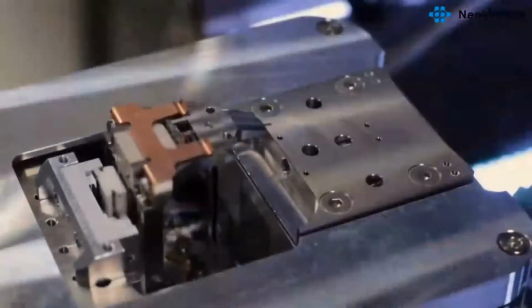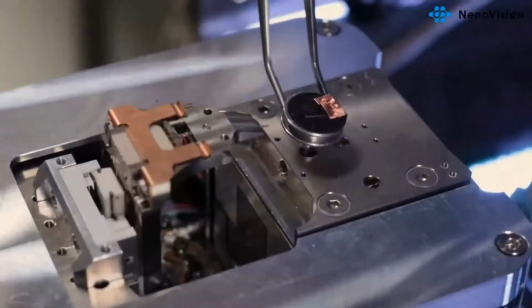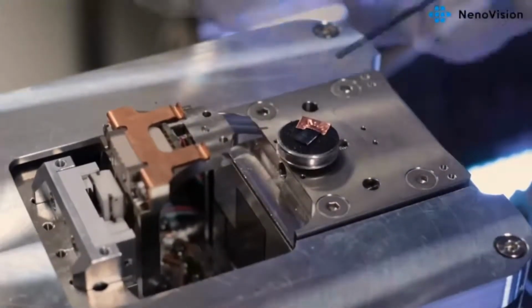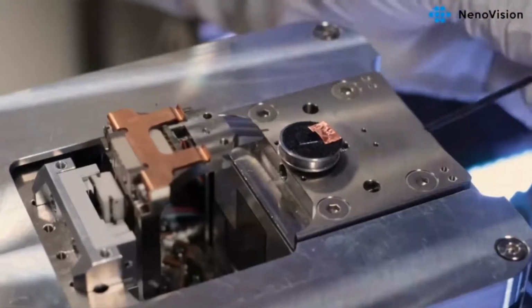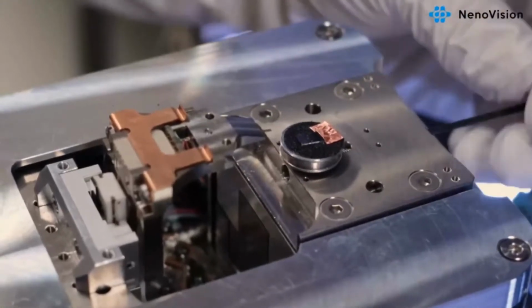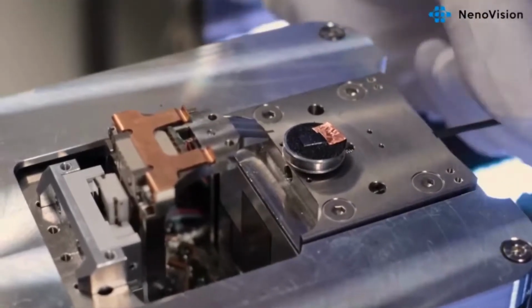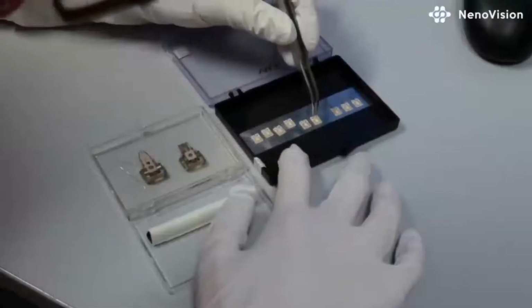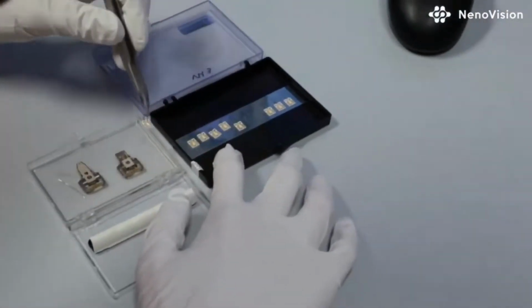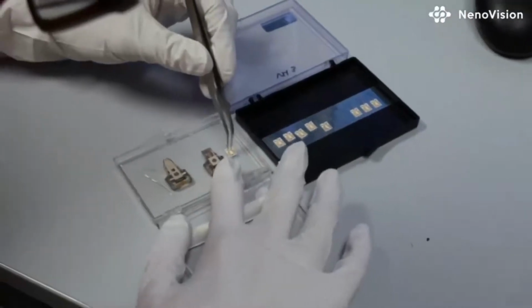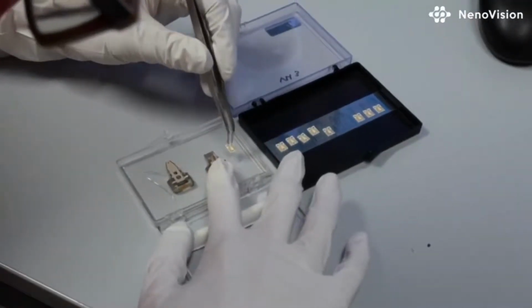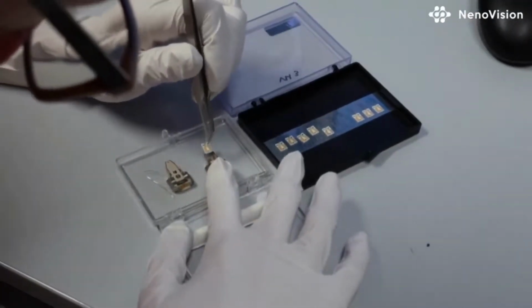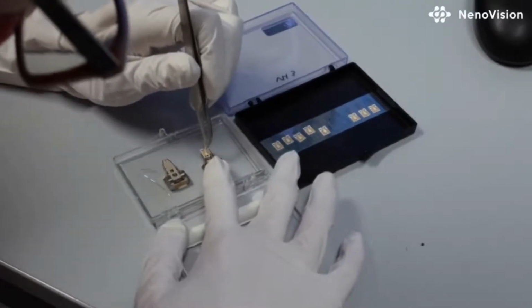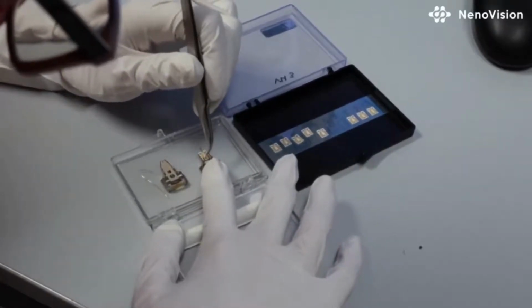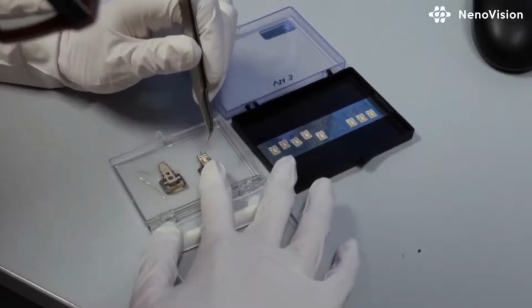Now it's time to load the sample and the probe. We fix the sample on an SEM stub by 1 little screw, exactly the same way as to the usual SEM sample holder. The probe, a commercial Akiyama probe, is placed into a probe holder, and using tweezers, we load the probe into the holder in the LiteScope.